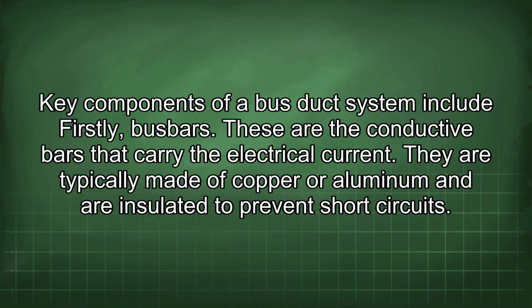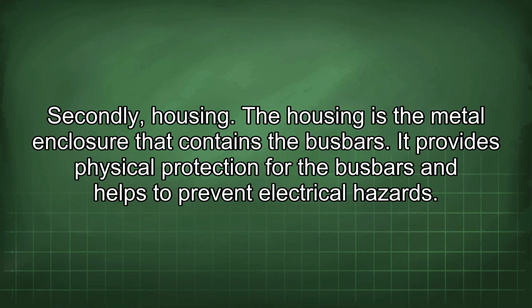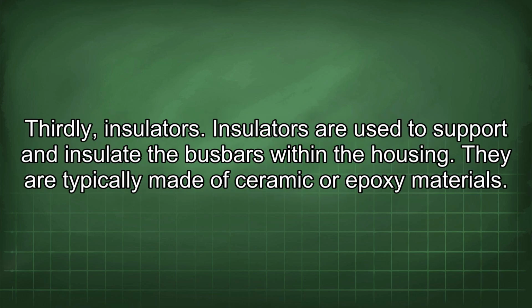Key components of a bus duct system include firstly bus bars. These are the conductive bars that carry the electrical current. They are typically made of copper or aluminum and are insulated to prevent short circuits. Secondly, housing. The housing is the metal enclosure that contains the bus bars. It provides physical protection for the bus bars and helps to prevent electrical hazards. Thirdly, insulators. Insulators are used to support and insulate the bus bars within the housing. They are typically made of ceramic or epoxy materials.